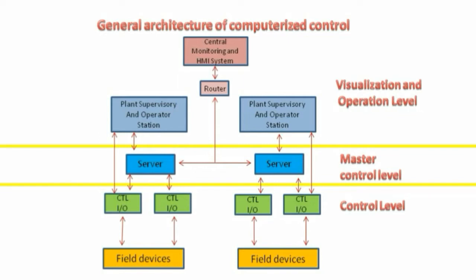Let's start explaining the architecture of the computerized control and the distributed control system. We start at a high level and as we go through the slides, we will go to more detailed explanation. At field level, we have the field devices such as pressure, temperature, and level sensors, feeding the signals through the input-output modules and the DCS controllers. The controllers will take the appropriate control action and feed the output to the final control elements.